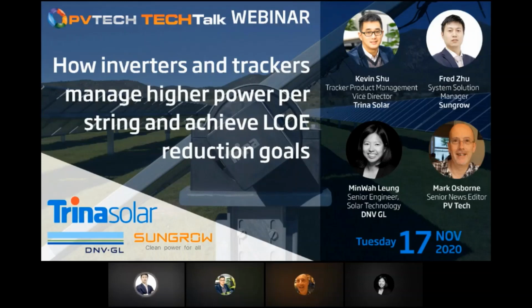Okay. Surely bifacial modules will cause a little bit higher mismatch loss because of the rear side. In fact, mismatch loss is a kind of cask effect. Mismatch loss consists of two parts. One is current mismatch within the string. The other is voltage mismatch between different strings. Furthermore, more than 90% of the total mismatch is from current mismatch. But unfortunately, whatever kind of inverter you choose, you can never solve the current mismatch loss. So it means that there's a very tiny difference between central inverter and string inverter for the mismatch loss issue, even though we use bifacial modules.